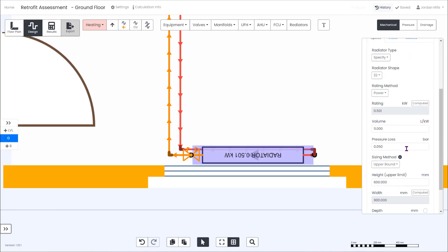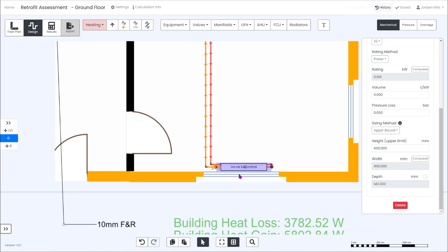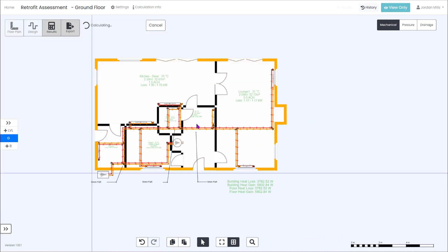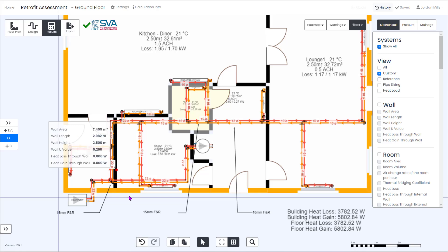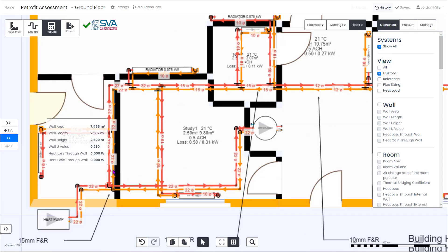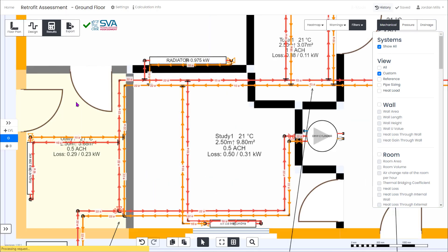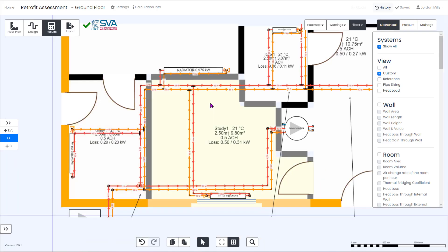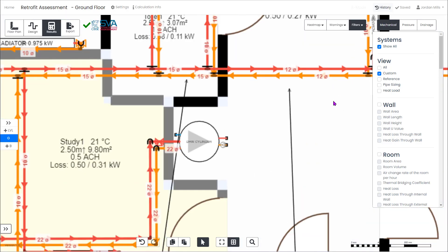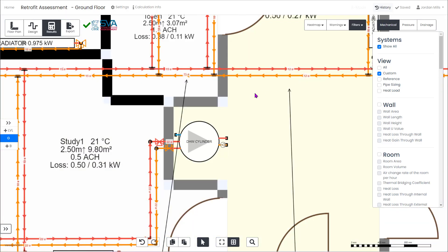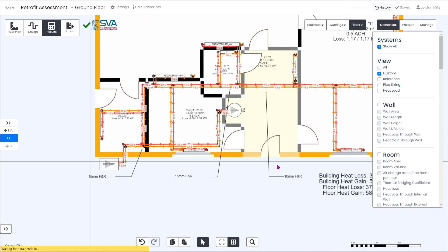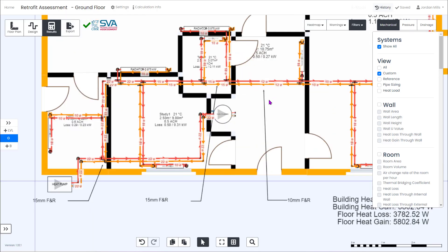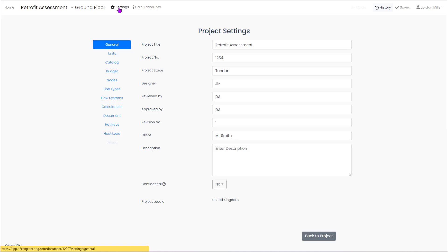And now that's in we can check the pipe sizes again. From the heat pump all the way to the study it needs a 22 mil pipe. Currently we have 15 mil so that section would need to be replaced. Across the hall it's calculated 12 mil where we currently have 10 mil. To replace all of this would be quite disruptive. We'd be going under the floor and four rooms out of six.